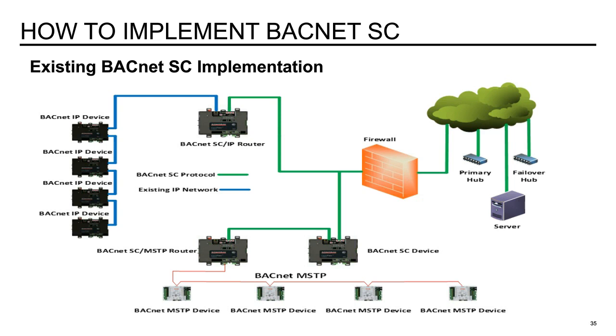Okay, great. And for our final question from Joseph, is there a limit on MSTP devices that can be connected to one router? I would say that's going to be dependent upon the manufacturer and what they allow. And that same would apply to a BACnet SC IP router. I'm not sure how all the manufacturers are doing their designs and implementation, so they could potentially have limits on the number of devices that they allow. But also keep in mind with an MSTP link, MSTP links only allow a certain number of controllers on that link. So that would also be a function of the MSTP installation as well.